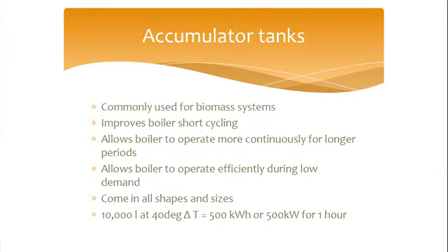I don't know, Christian, have you got a rule of thumb for litres of water per kilowatt of demand? I know in solar they do 10 litres per kilowatt, but they come in all shapes and sizes, from 10,000 litres. So a 10,000 litre tank at 40 degrees delta T will hold 500 kilowatts in it. So you've got a 500 kilowatts for 1 hour sort of battery that you can use.